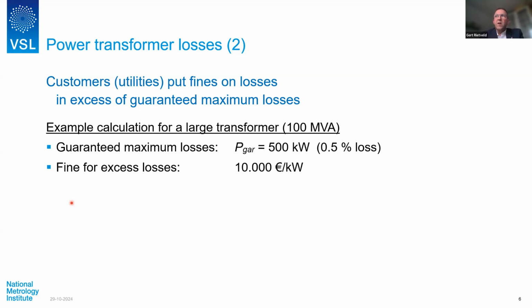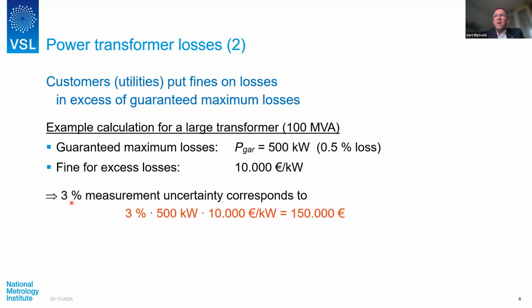Then the typical fine is €10,000, $10,000, this order of magnitude per kilowatt that is above the agreed guaranteed maximum losses. So assume you now have a 3% uncertainty in your measurement, then 3% of my losses, 500 kilowatt, times this fine adds up to €150,000. So already the measurement uncertainty of 3% corresponds to a very significant amount of money. And mind you, this is 3% of 0.5%.